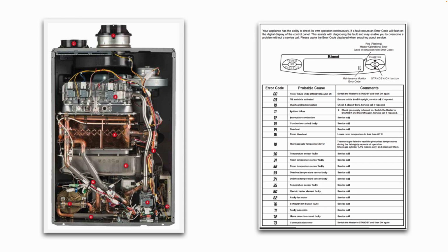And all water heater manufacturers will usually give you an error code chart or key, which tells you if the screen is flashing an error code, for example, 00, probable cause is a power failure while standby switch on. Switch the heater to standby and then on again. And you can look down this list. There can be several error codes that can occur with these tankless water heaters. Some are more complex than others. Some are more difficult to fix, more expensive to fix than others.